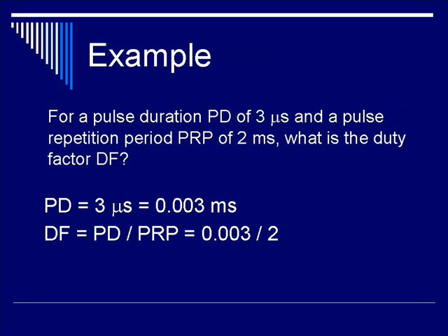Duty factor is therefore PD (0.003 milliseconds) divided by PRP (2 milliseconds). This simple ratio gives a DF of 0.0015, which can also be written as a percentage by multiplying by 100, giving 0.15% as the duty factor — which is in the range mentioned earlier.